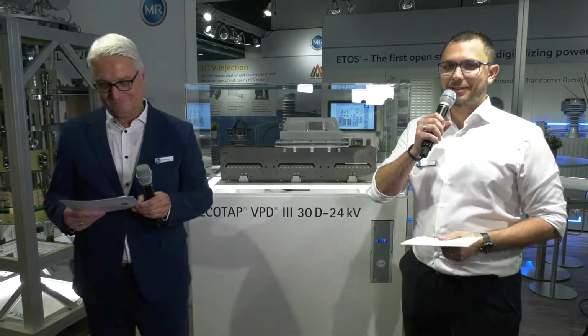The distribution network faces more and more challenges due to the energy transition. Some reasons: decentralized generation, like rooftop solar or batteries associated with virtual power plants, directly connected to low or medium voltage, which increases production and reverse power flow. There are also new consumption habits like electrical heat pumps or EV charging, creating additional peak consumption which loads the distribution network, especially on the low voltage side.